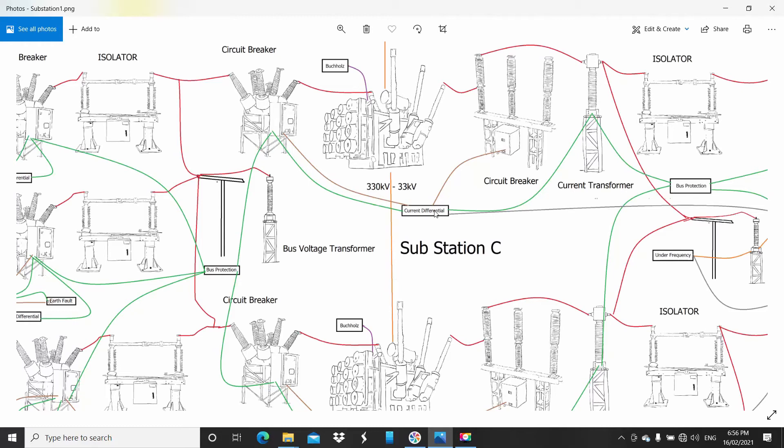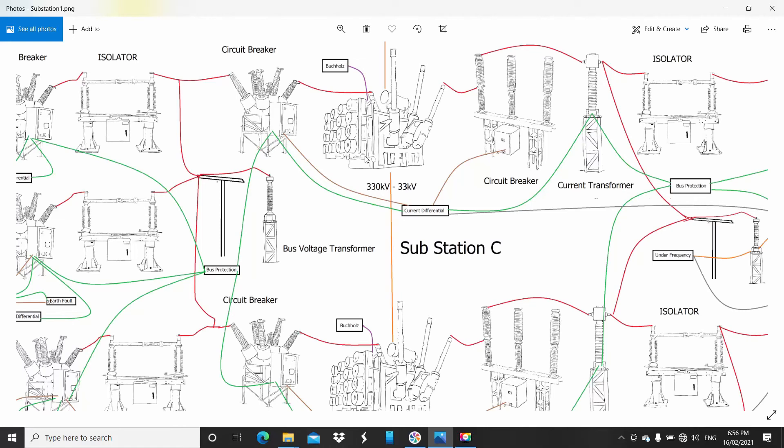To overcome this, you can balance it by having the ratios match. They won't be the same, but what I mean by matching is you'll have one at say a thousand and one at a hundred, if it's like a ten to one ratio. That way the current is the same. So what would happen is if there's a fault inside the transformer and the power that's going into the transformer is not going out the other side, then you know you've got a problem. It trips out.